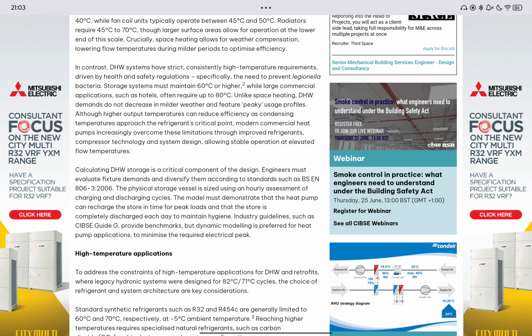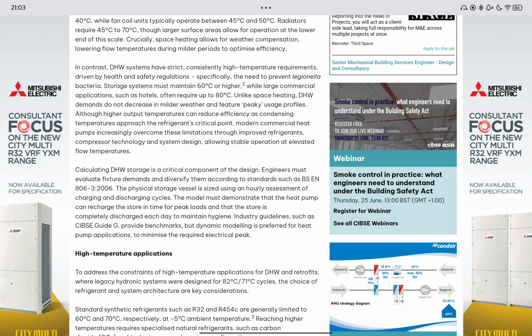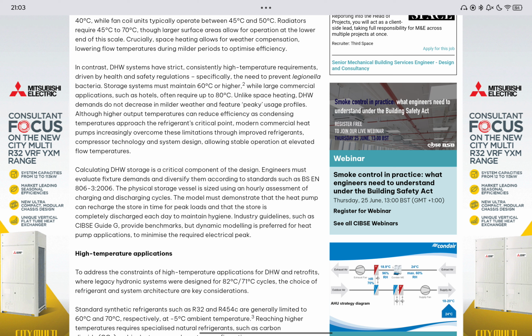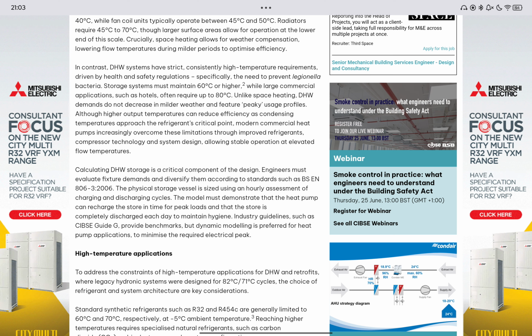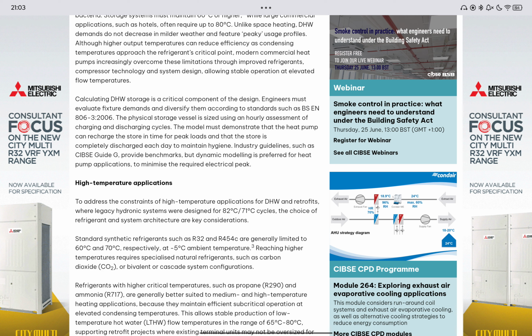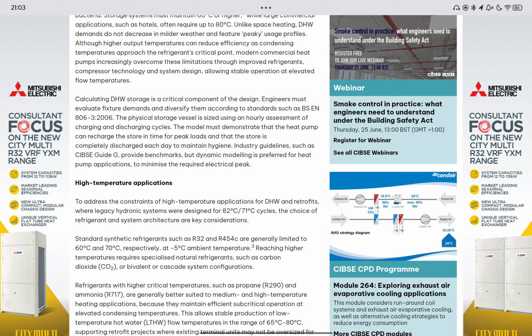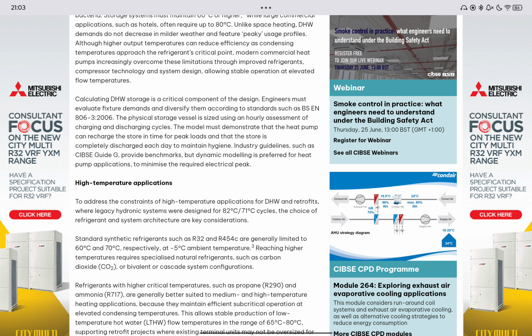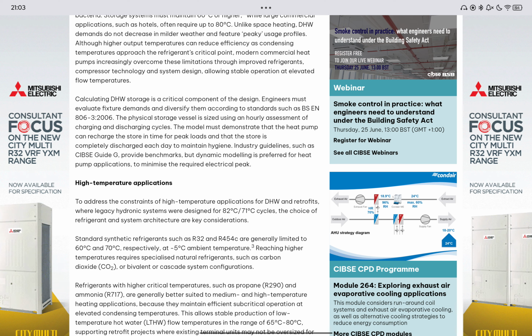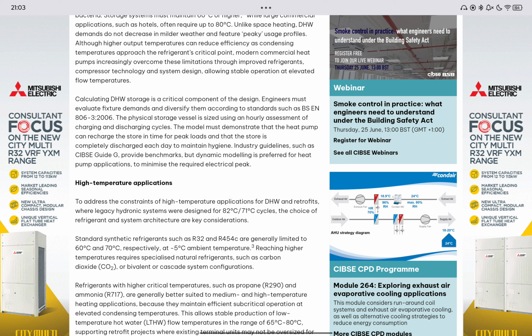Although higher output temperatures can reduce efficiency as condensing temperatures approach the refrigerant's critical point, modern commercial heat pumps increasingly overcome these limitations through improved refrigerants, compressor technology and system design, allowing stable operation at elevated flow temperatures. Calculating DHW storage is a critical component of the design. Engineers must evaluate fixture demands and diversify them according to standards such as BS EN 806-3 2006. The physical storage vessel is sized using an hourly assessment of charging and discharging cycles.